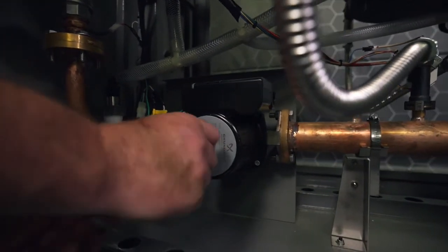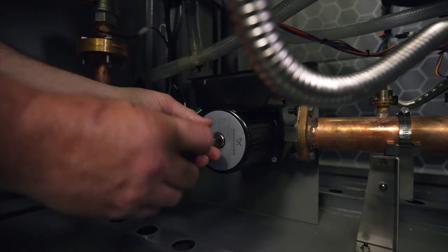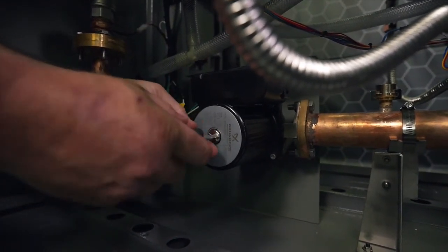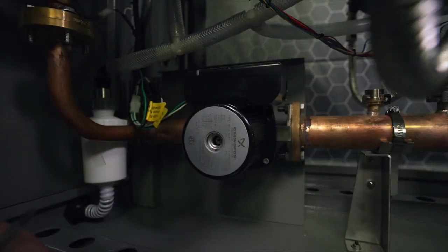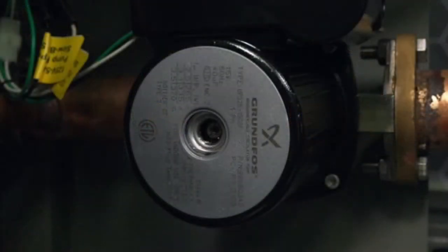You will then want to remove the 1 inch flathead screw on the side of the pump. This will bleed the pump of air in the system and will allow you to see the shaft on the inside. You should be able to see the shaft turning.